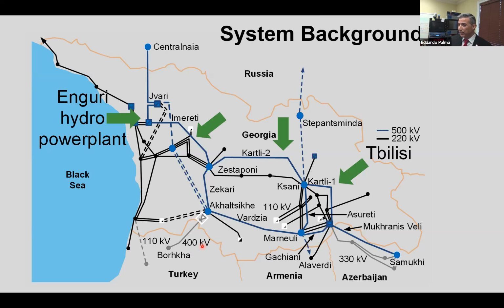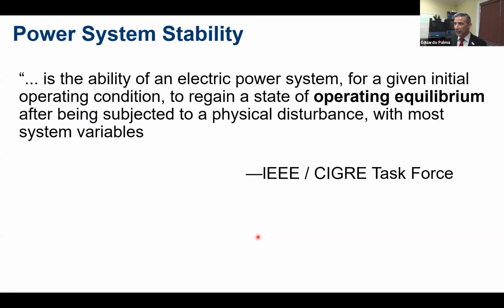So as you see here, there's not only one way for the 500 kV lines to connect to the main capital, but there is a second path for 500 kV, making it a ring. A ring stabilizes the possibilities for this path not to be broken. But at the same time, we have to compensate the power that is generated with the loads that are consuming this power.